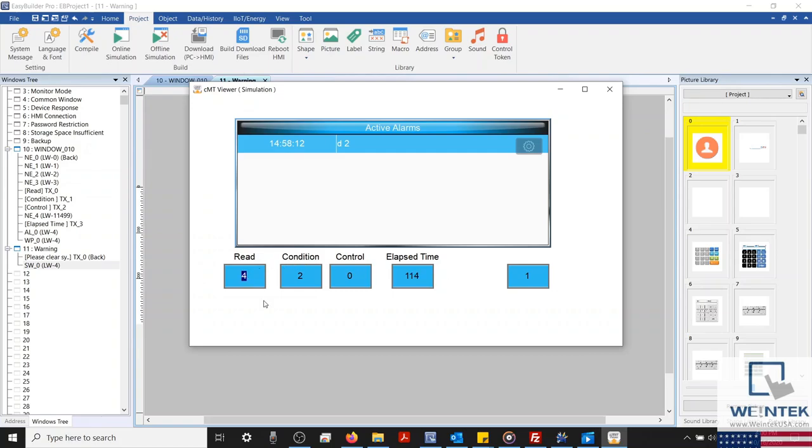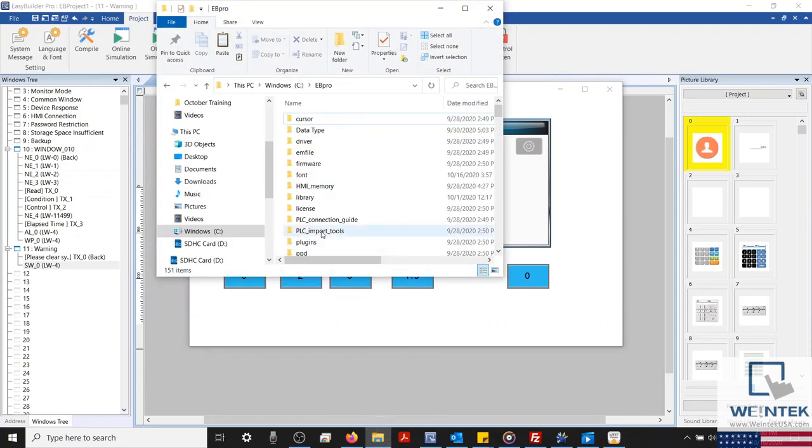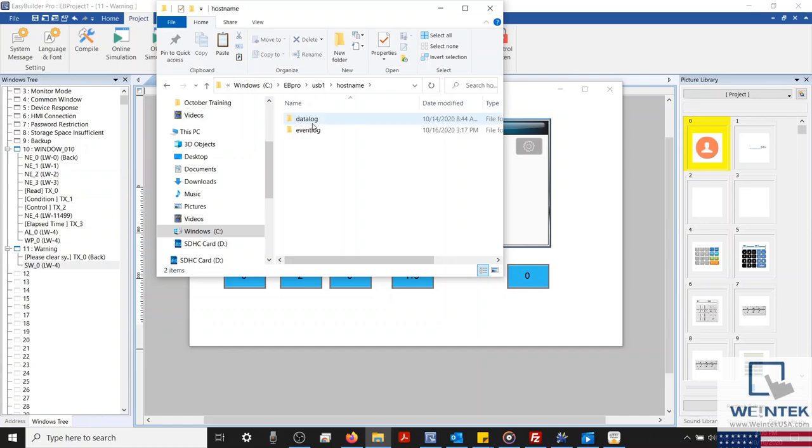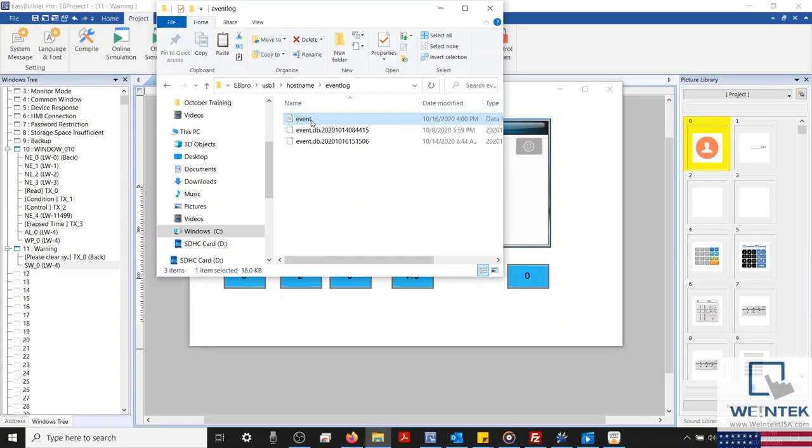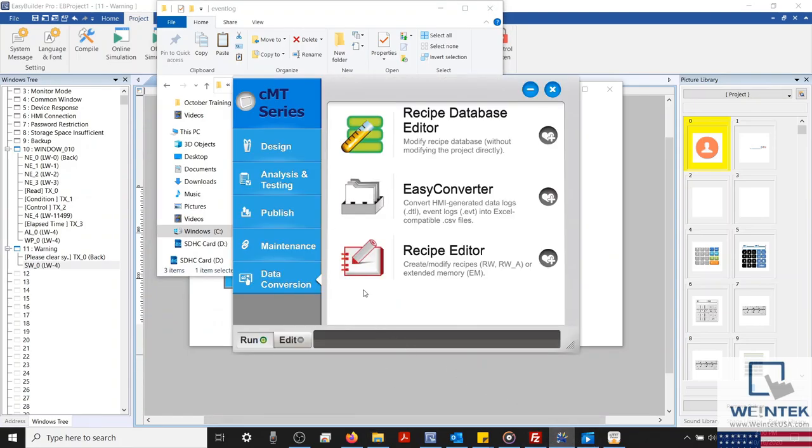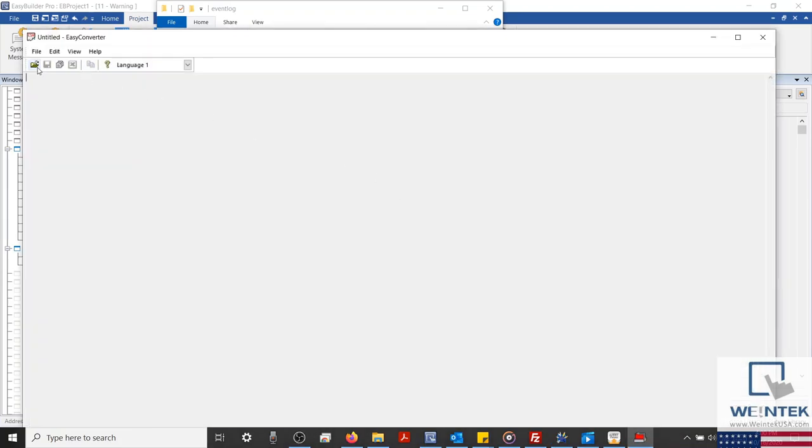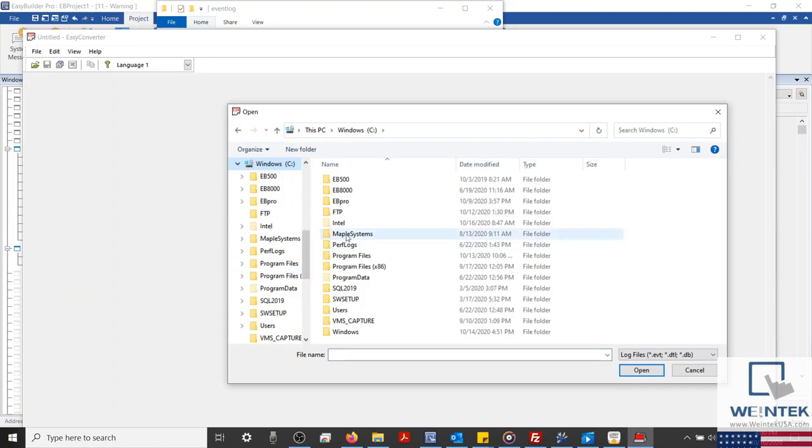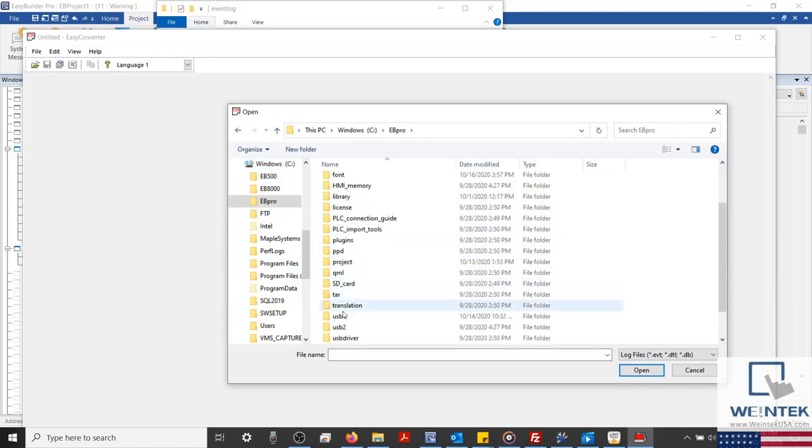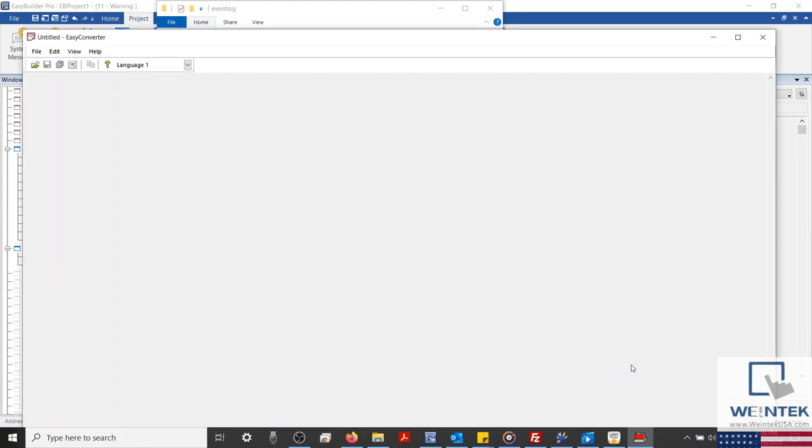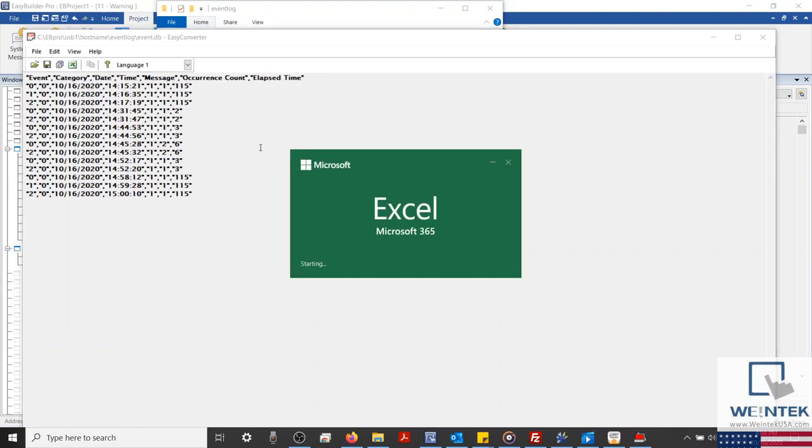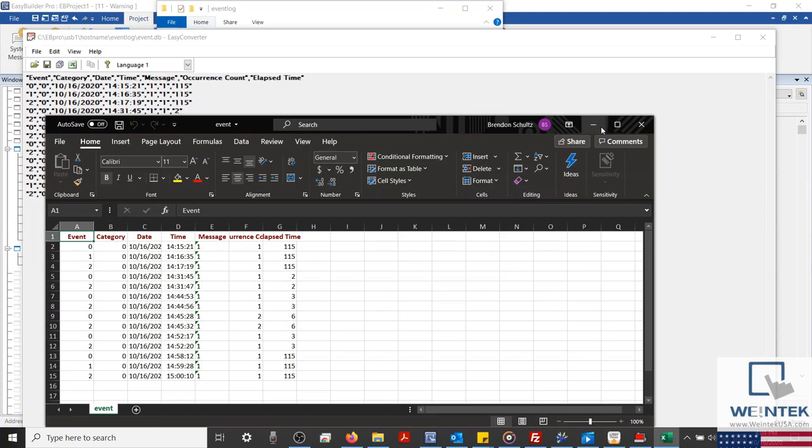Now, let's clear our alarm and use our control address to sync our data to our USB. To do this, I'm going to submit a value of 2 into our control register. Within the EasyBuilder Pro installation directory, we can look through the contents of our USB, and we'll find our event information in the form of a DB file. Using EasyConverter, an application accessible within our Utility Manager, I'll open this file and convert this to an Excel sheet. Where we can then view our stored data.